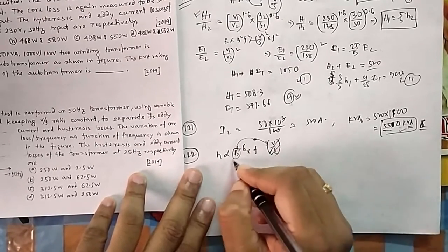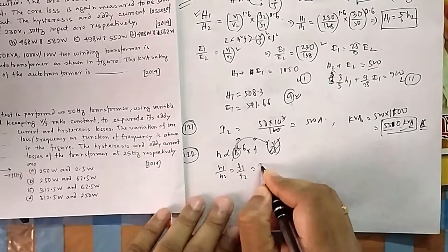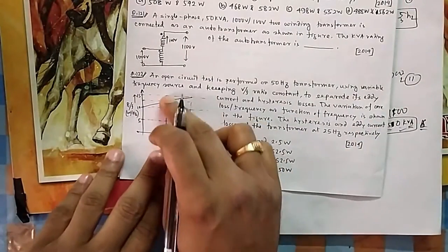You know your hysteresis loss is directly proportional to B to the power 1.6 times f. Now B is equal to V by f. B is directly proportional to V by f. Now this V by f is kept constant, that means your B is kept constant. So your H1 by H2 will be only f1 by f2.